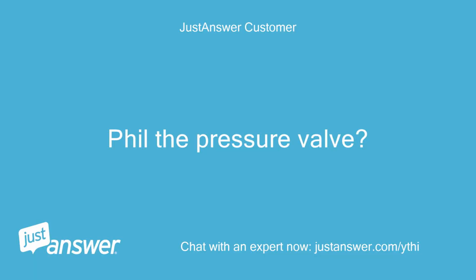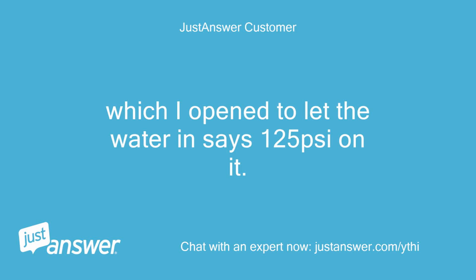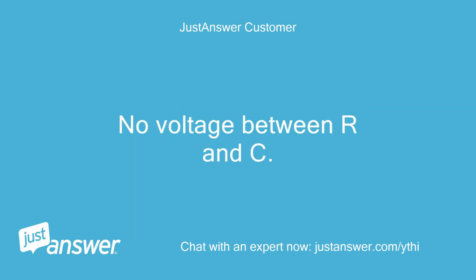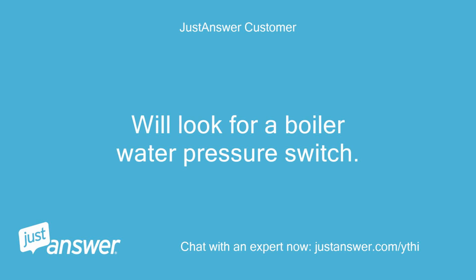Fill the pressure valve, which I opened to let the water in, says 125 pounds per square inch on it. No voltage between R and C. We'll look for a boiler water pressure switch.